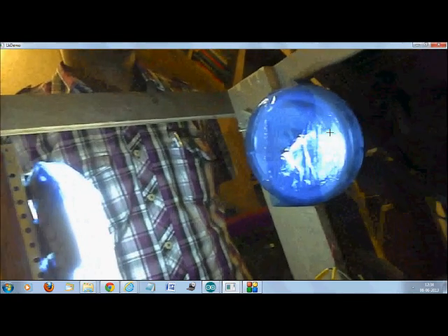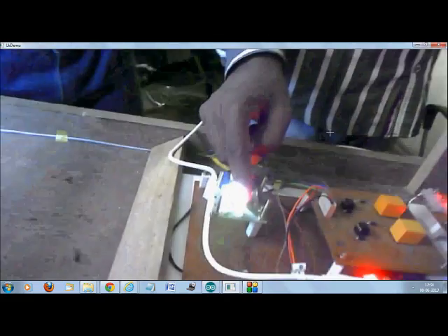Now, if that is the case, you can see one light is turned off. We say that whenever temperature is increased, we do not want to flood the child with too much light. So we reduce it, and whenever the temperature starts getting normalized, the buzzer should be off and the light should come back to normalcy. The camera is not showing the LCD value properly, so if I can read it to you, the temperature value is reading around 40, and then it has come back to normalcy, and every time there will be changes.